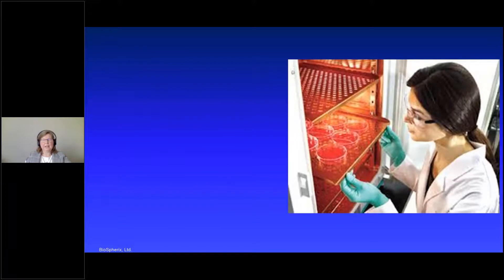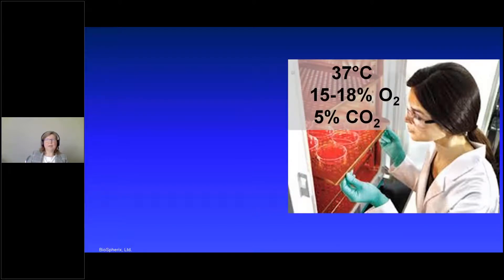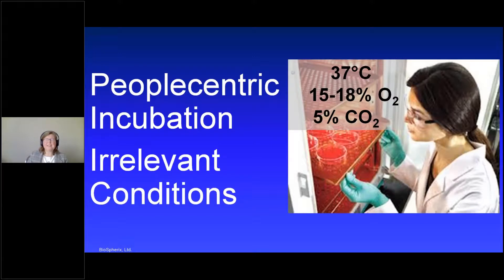A lot of people start with this image — a traditional cell culture incubator — and I'm going to make the case that it is designed for the needs of people, not the needs of the cells. It's easy to get your hands in there and your face right in there. But there's that water pan in the bottom that's always contaminated and poses a contamination risk. The oxygen in here is all wrong — way too high for the levels that cells, even normal cells, experience inside our bodies. The CO2 is there only as long as the door is shut. Every time you open the door, the CO2 goes off and the pH goes off — whether it's you or someone else in the lab accessing their cells.